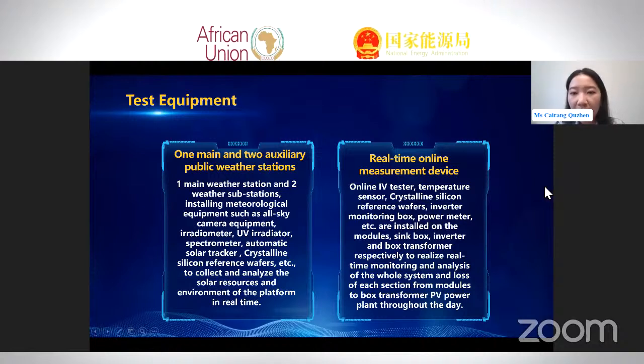For the real-time online measurement devices, we use online IV testers, temperature sensors, crystalline silicon reference cells, inverter monitoring boxes, power meters, etc. These are installed on the modules, combiner box, inverters, and box transformer respectively to realize real-time monitoring and analysis of the whole system and losses of each section from module to box transformer throughout the day.